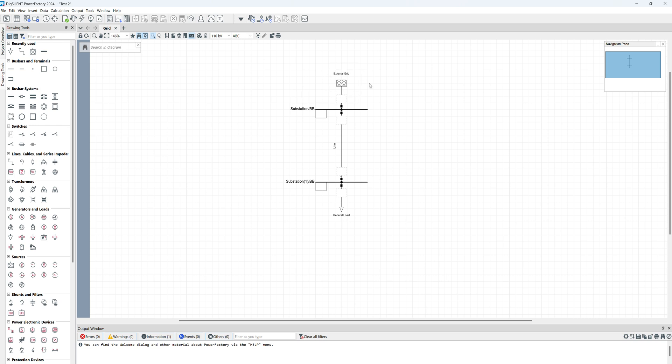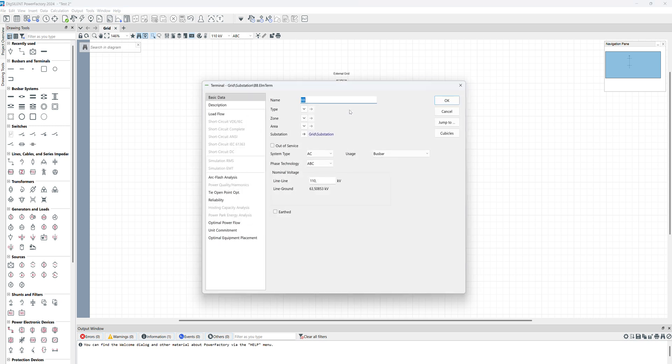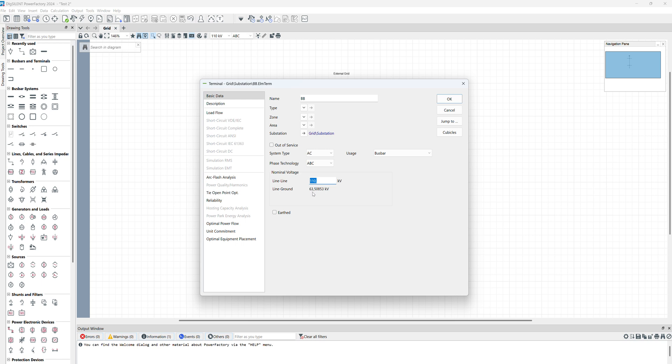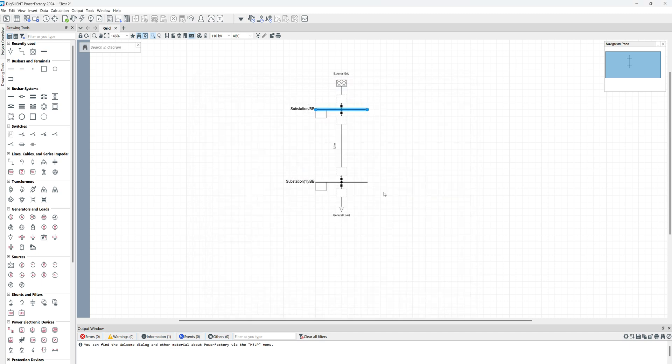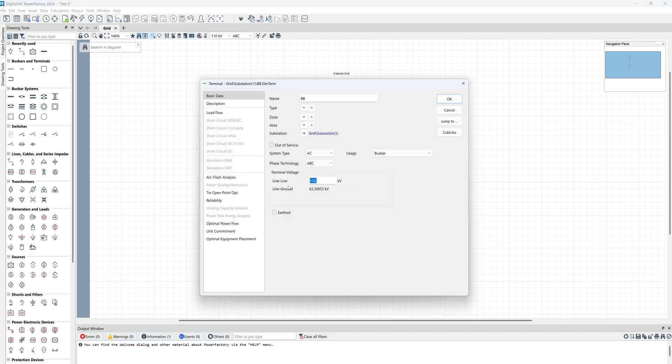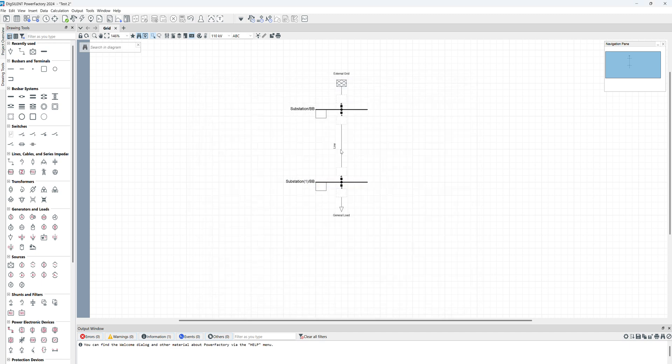Now we have the model but we didn't put any specification for this model. External grid is something universal so you don't need to change anything for that. Here we have bus bar. We should change the voltage. If you double click on that, here we have voltage level line to line. For example, you want to change it to 10. If you change this line to line voltage, the line to ground is automatically calculated. Click OK. Here is the same voltage and here we have line.